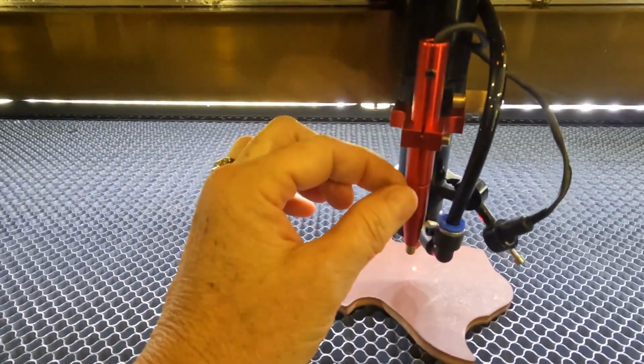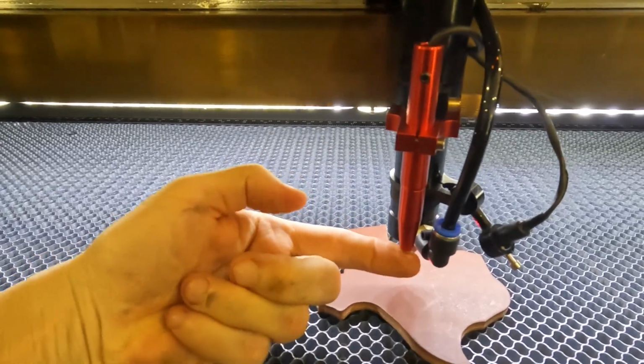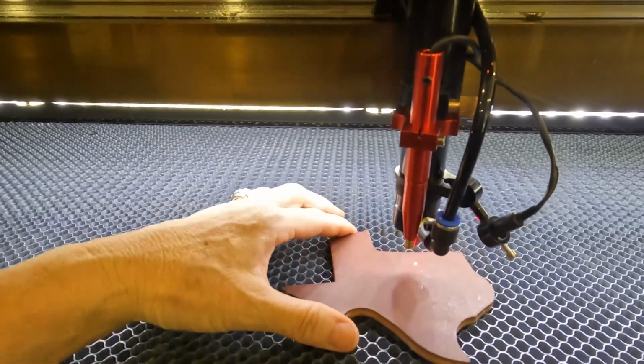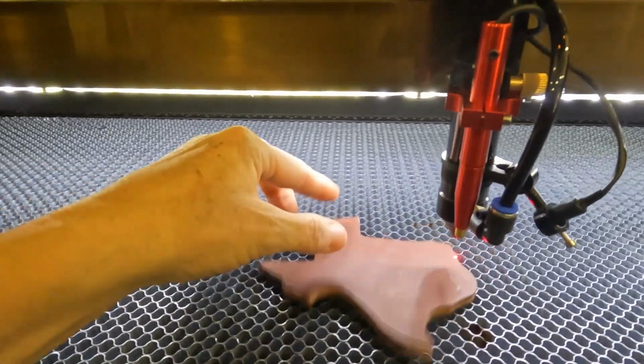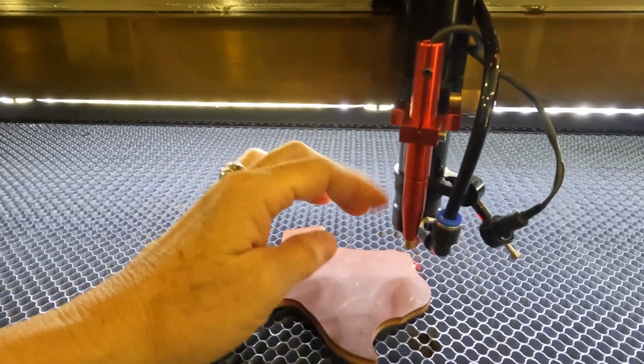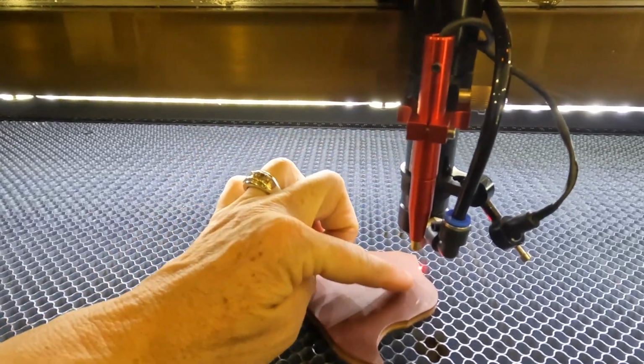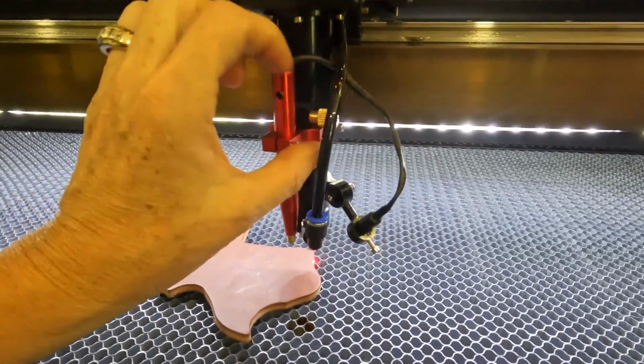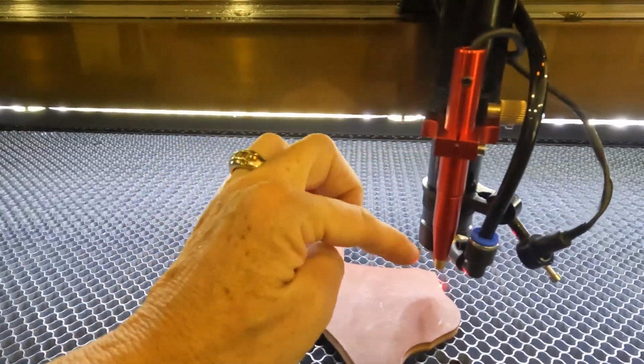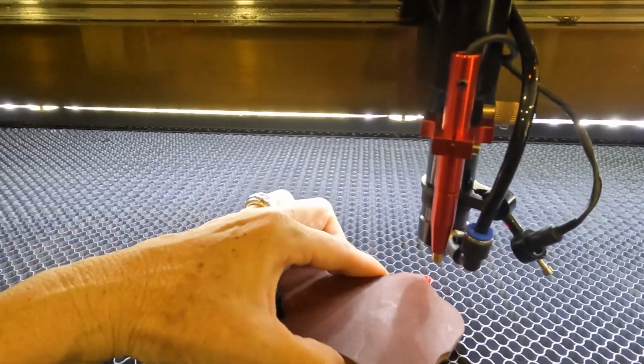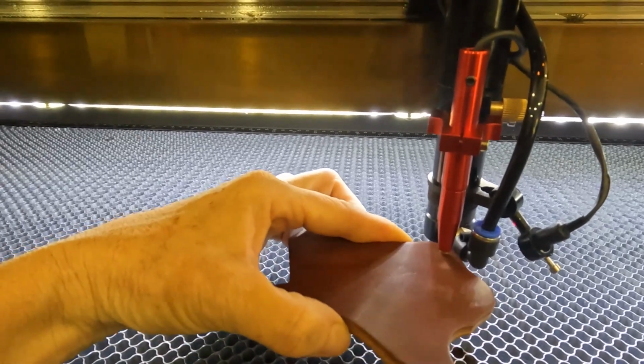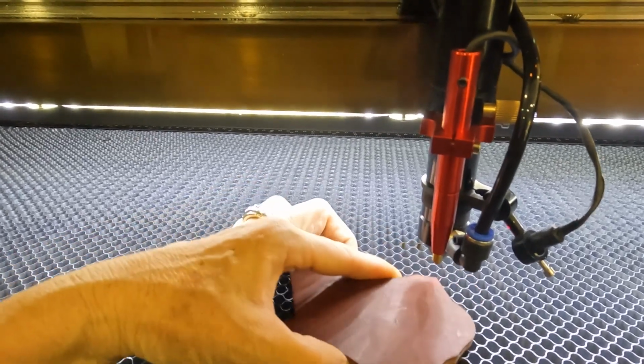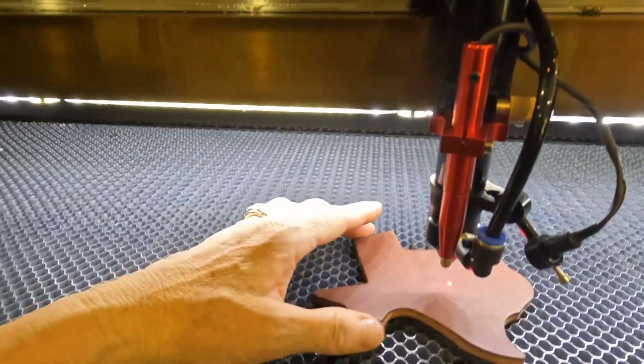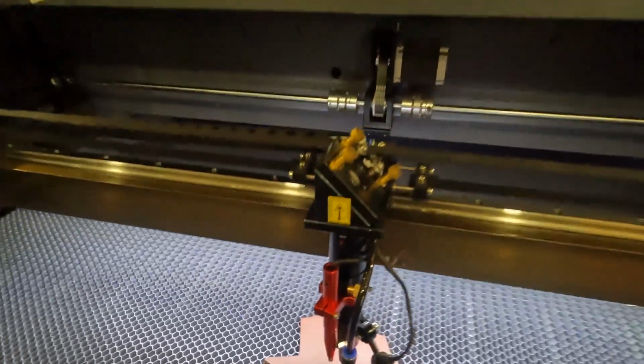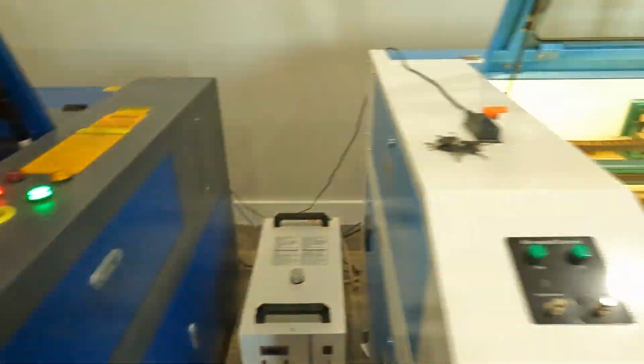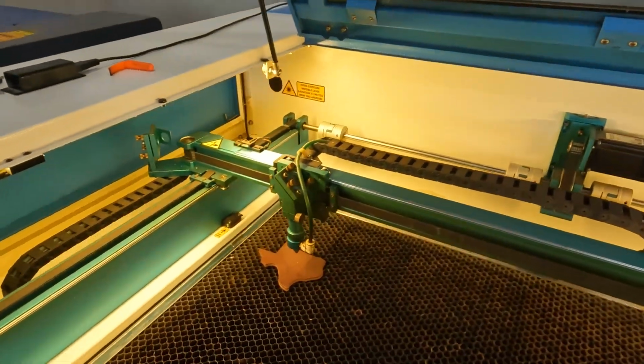Let's look at the autofocus. This is the autofocus arm. And so this works where you would raise the bed. I don't have it in the right position, but you could lower the autofocus to a certain depth. You would lower it with this nozzle here, or that knob there. And when the material came up and hit that, then it would say, don't go up anymore. So that's the autofocus design on this machine. I never use autofocus. I would not encourage you to do that, but I'm showing you the different systems.